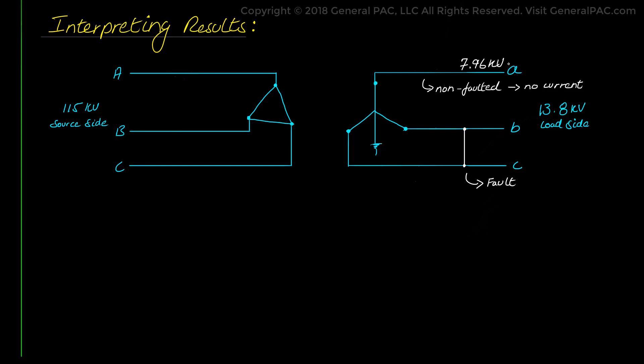However, for the faulted phases at the point of the fault, and now we are talking about phase B and phase C, the fault voltages are exactly half, meaning it is 7.96 kV divided by 2 or 3.98 kV phase voltages. Now this is an interesting characteristic which is quite common for a classic line to line fault in power systems.